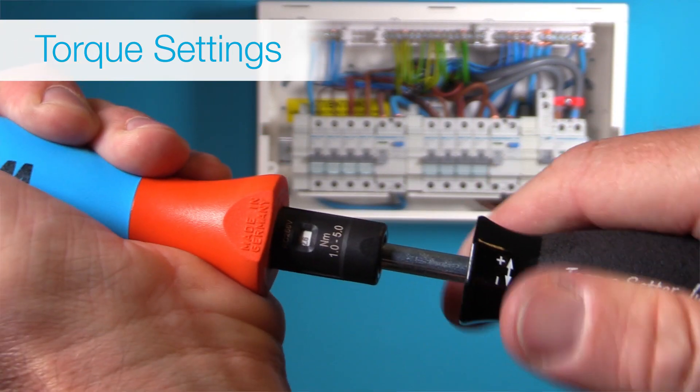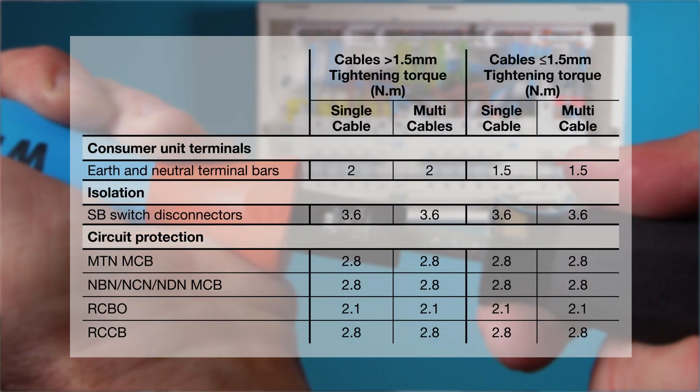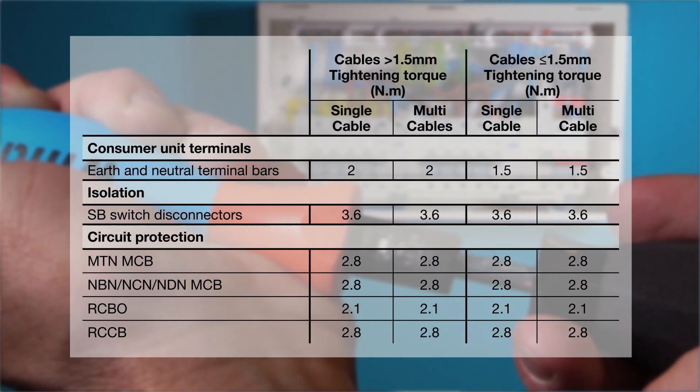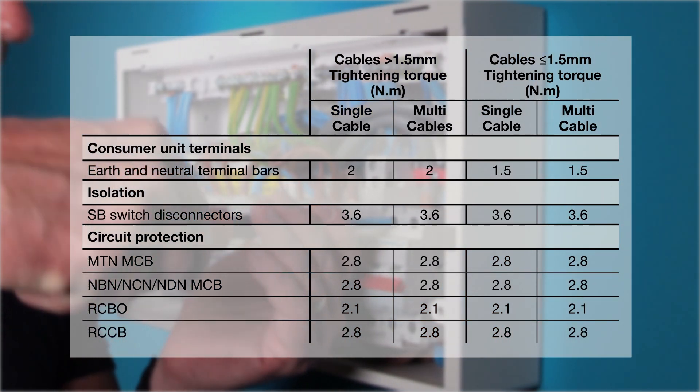Recommended torque settings should be used to ensure that a sound electrical connection is achieved. Please note that on cables 1.5mm² and below, Hager recommend doubling the conductor over.